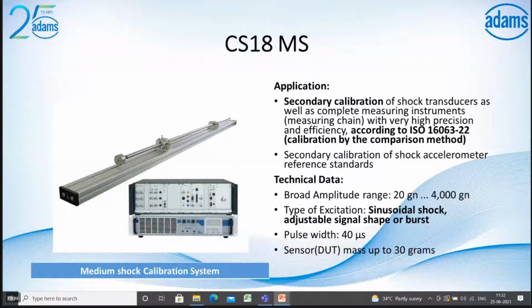CS18MS, it's a medium shock calibration system. It's a secondary calibration system according to the standard ISO 16063. It's a comparison method for the calibration of shock accelerometers. The maximum range you can go up to is 4000 G, and for the type of excitation you can give either a sine shock or burst. The maximum pulse width is up to 40 microseconds for the medium shock calibrations.